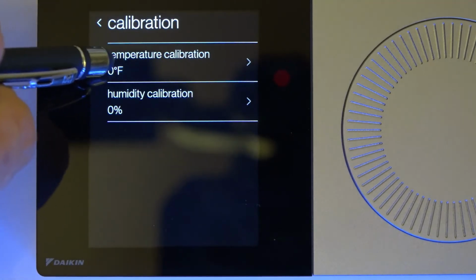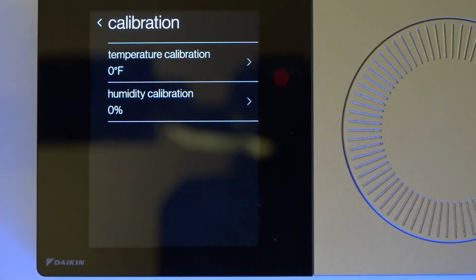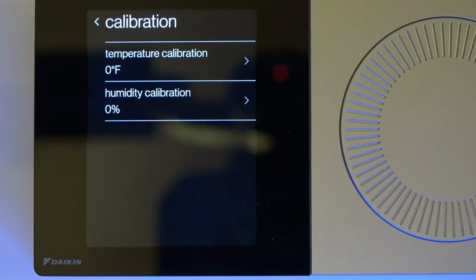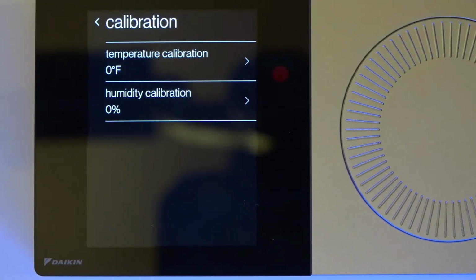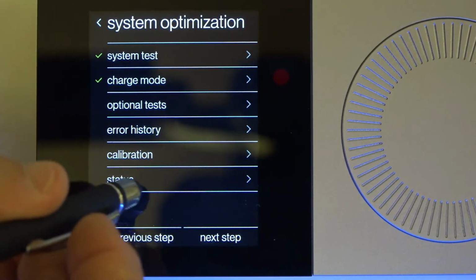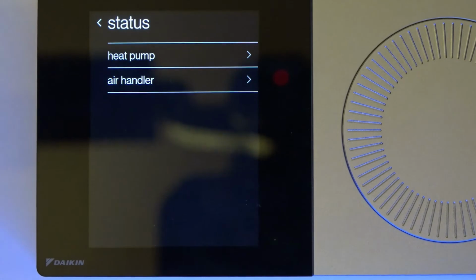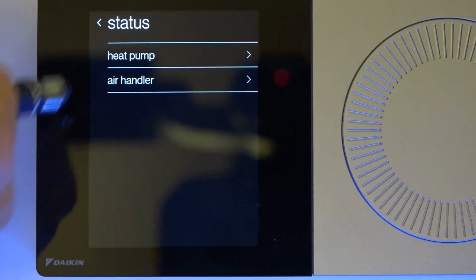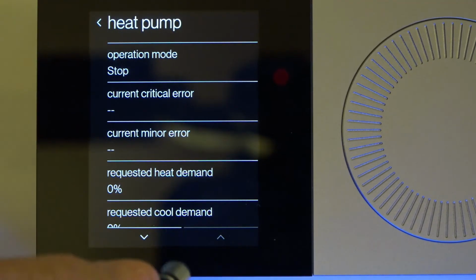So I can hit calibration. I can do a temperature offset or a humidity offset. But the key to properly calibrating this thermostat is having it off for 30 minutes, powered up, but no heating or cooling call for 30 minutes before you calibrate it. Other than that, I've got a status screen here. I can hit the heat pump, which is the outdoor unit here.